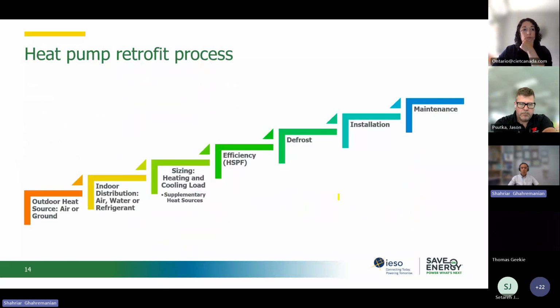But let's look at how we should approach a heat pump retrofit, and what steps we need to go through. So let's start first of all from the outdoor unit. We need to first think of what outdoor sources we want to use. First, and the most common one, is the air. That means we extract heat from air in the winter season, and we dump extra heat from inside of the building in the summer season, again back to air. So this is an air source heat pump, and we can use that one.